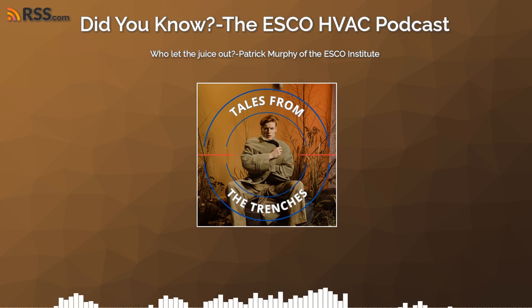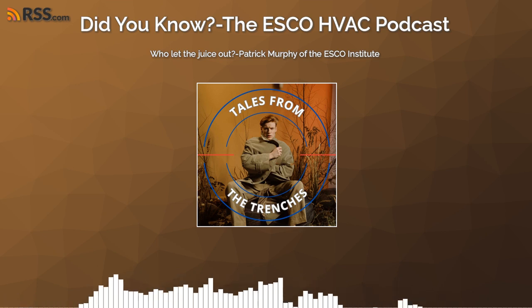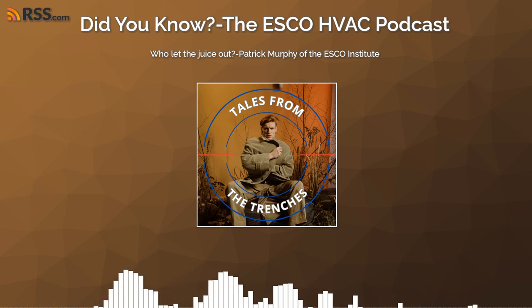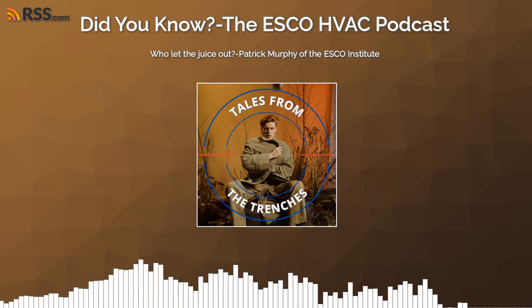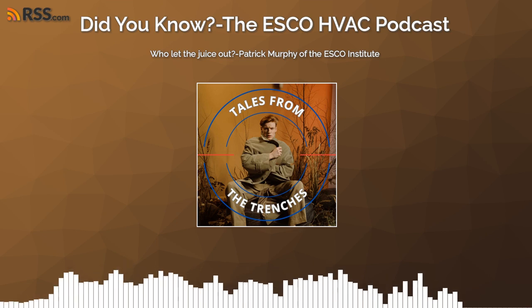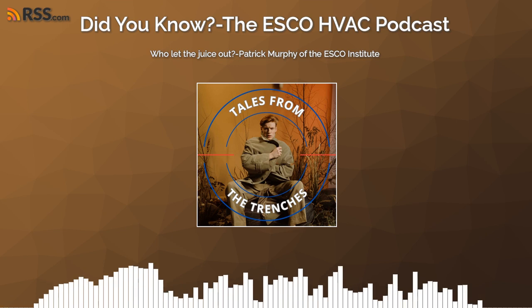You walk up on the roof and you're looking at the condensers — you can literally stand inside these condensers — but looking from the outside, they look clean. Then you turn around and behind you there's an earth-moving device clearing some land, and dirt and dust is wafting across the top of the unit. They're converting an old drive-in movie theater into a housing development. The dust has just finely coated the condensers — super fine dust. Now I'm starting to paint the picture.